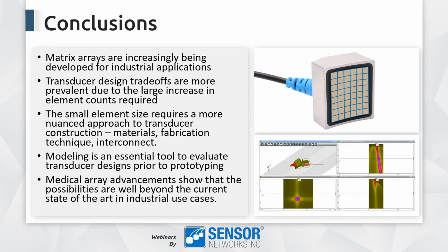So some concluding remarks. Matrix arrays, of course, are increasingly being used and developed for industrial applications. There are many trade-offs in the designs, mostly based on the channel count. We always have limited numbers of channels to work with based on the systems we have, and so we have to decide how to, in a smart way, break these apertures up into a matrix of elements and get the performance that we're looking for.